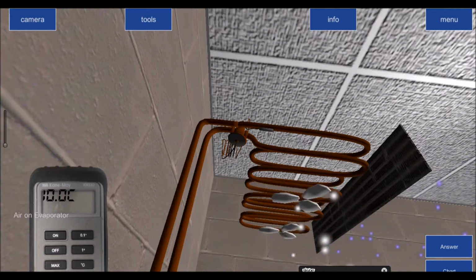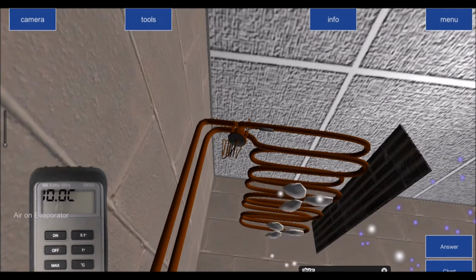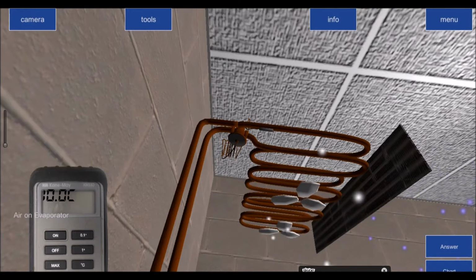So air on, it should be 5 to 10 degrees lower. If I have air on of 10 degrees, I need an evaporating temperature of 5 degrees. If I take 6 off 10, it's going to be 4 degrees. If I take 7 off 10, it's 3 degrees. If I take 8 off 10, it's 2 degrees. If I take 9 off 10, it's 1 degree. And if I take 10 off 10, it's 0 degrees. So my lowest evaporating temperature should be 0 degrees, and my highest should be 5 degrees.